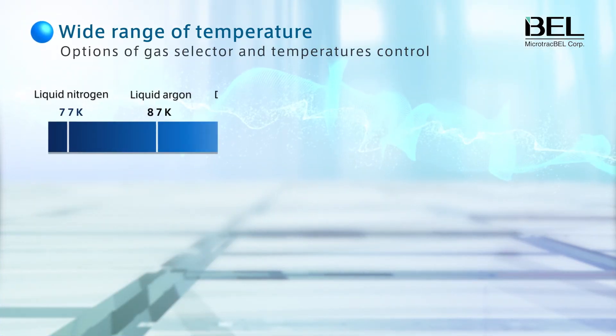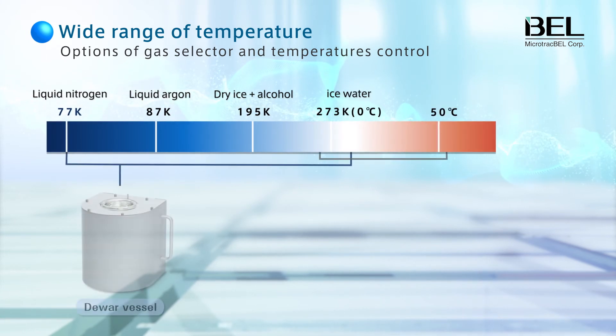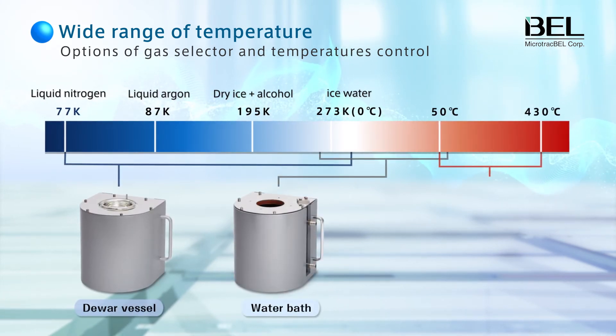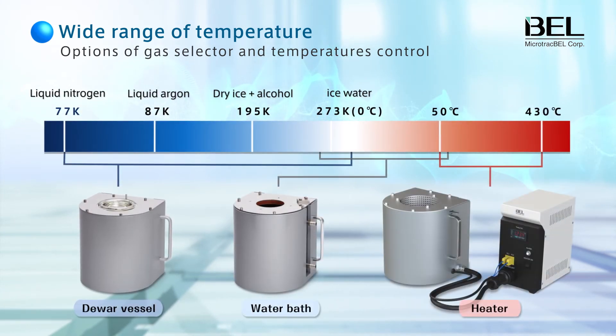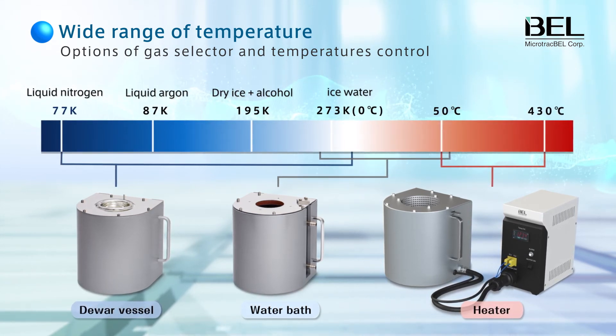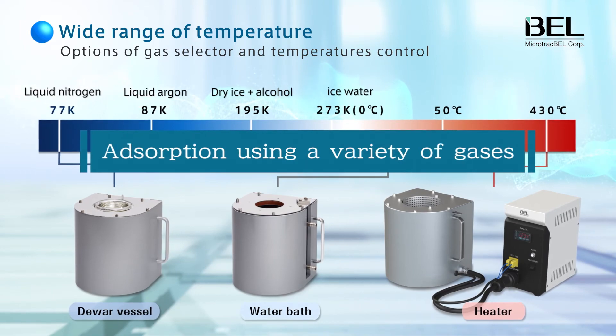Using a Dewar vessel, a water bath, or a heater gives you a wide measurement temperature range from 77 Kelvin to 430 degrees centigrade. And by combining the Belsorp Mini-X with a gas selector, a wide variety of gases can be used.